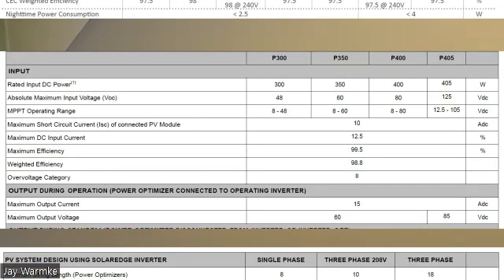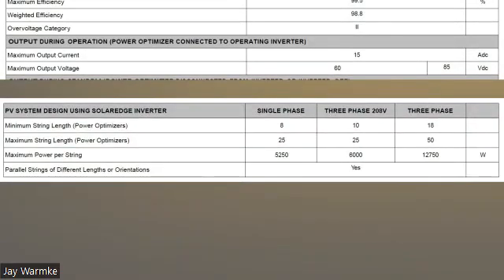And what is the voltage operation, or the maximum voltage for these optimizers? Down at the bottom of this chart, 60 volts for most of them, 85 volts if you get the P405 optimizer unit. So they do have a maximum voltage tolerance. And what they do to maintain that voltage, or not to exceed that voltage when they're all in a string, is they have a minimum number in a string and a maximum.